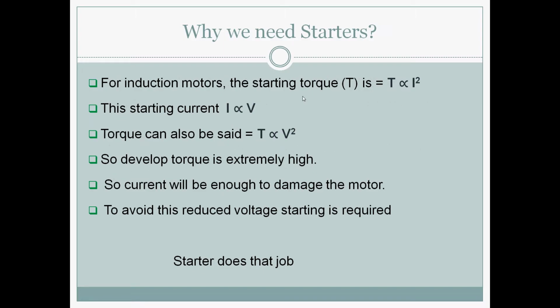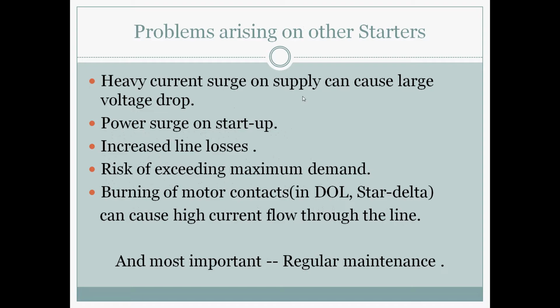Coming to the basics, why we need a starter. For an induction motor, the starting torque is proportional to the current square. Again, current is proportional to V, voltage. So you can say that torque is proportional to V square. So developed torque is extremely high, and the current will be enough to damage the motor. To avoid that, reduced voltage starting is required, and the starter is doing that job.